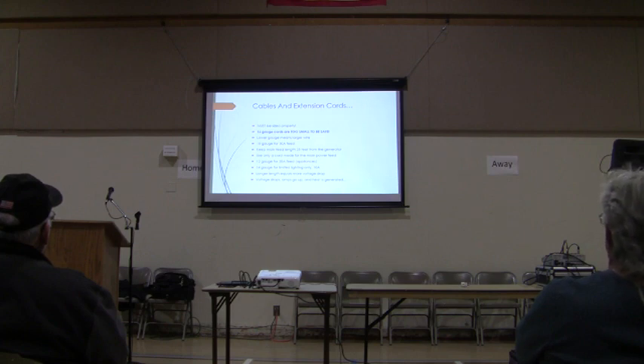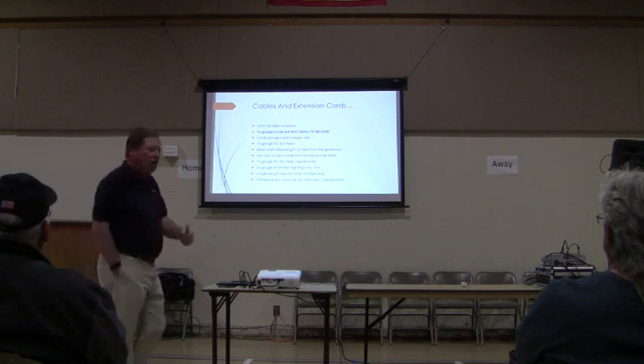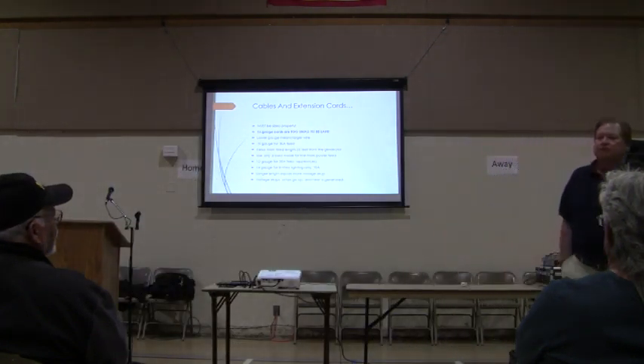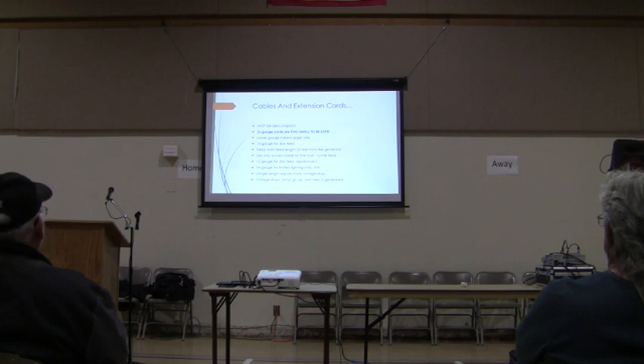Use only a cord made for the power feed. 12 gauge will feed a 20 amp circuit at most. You may see a lower number on your cable, right, Gary? Gary just bought one. He got a 12 amp cord and it says 12 gauge cord. It says 15 amps. 14 gauge for limited lighting only, 10 amp circuit. Your refrigerator is on at least a 15 amp, if not a 20 amp breaker. Same thing with your furnace. Longer length means voltage drop. Voltage drop, amps go up, and heat is generated.